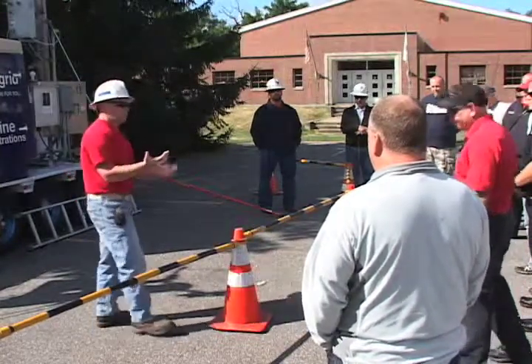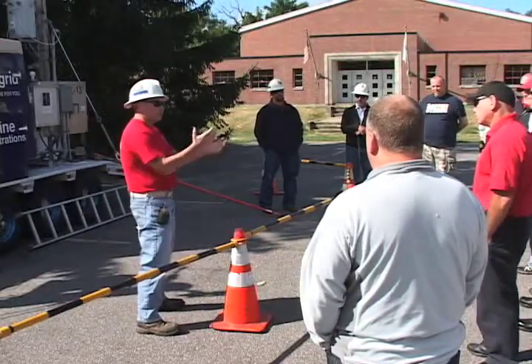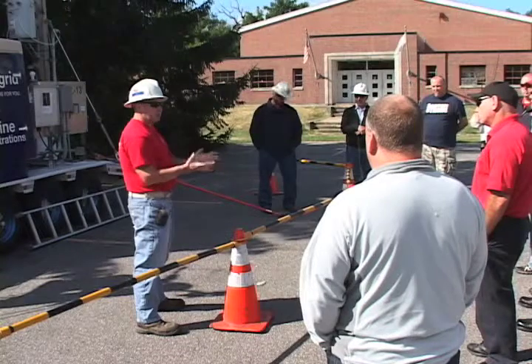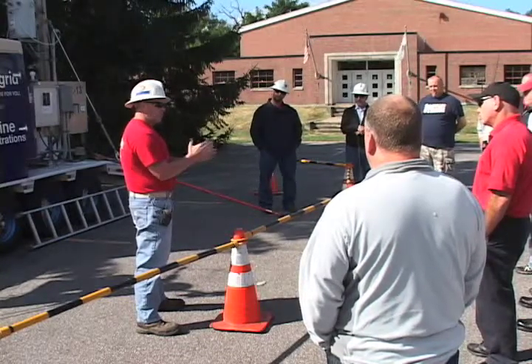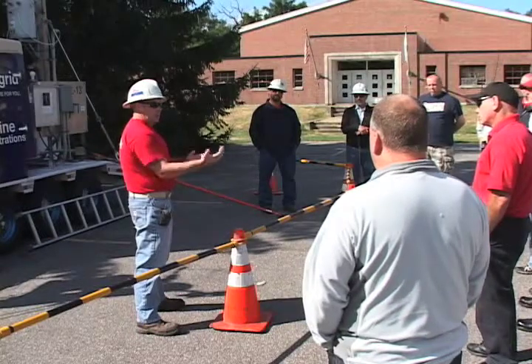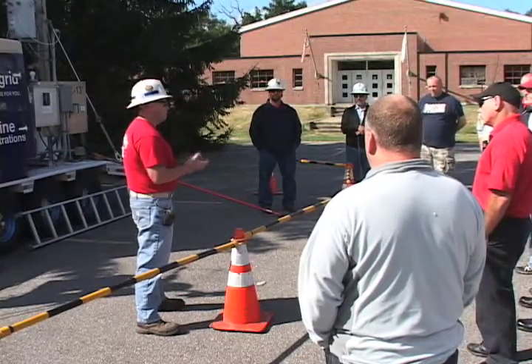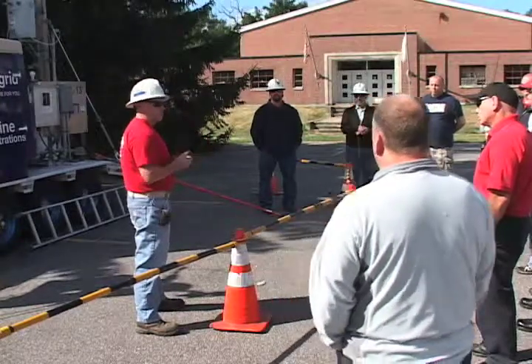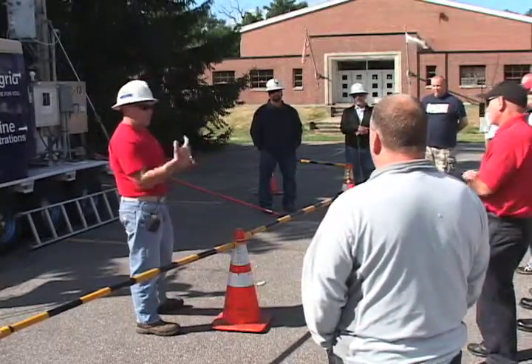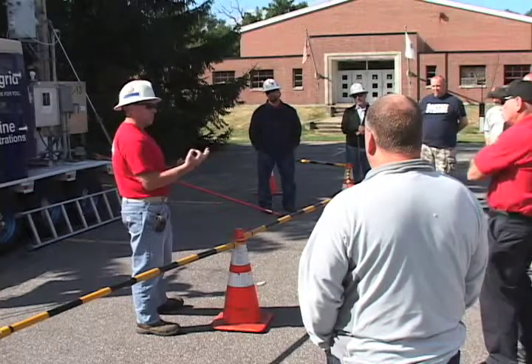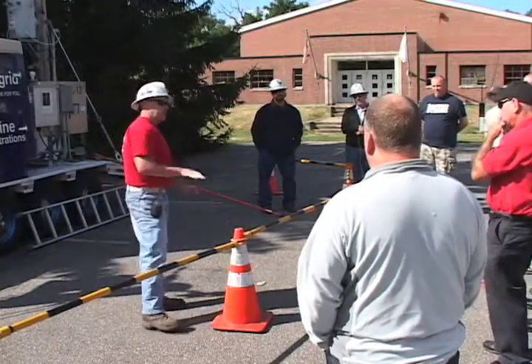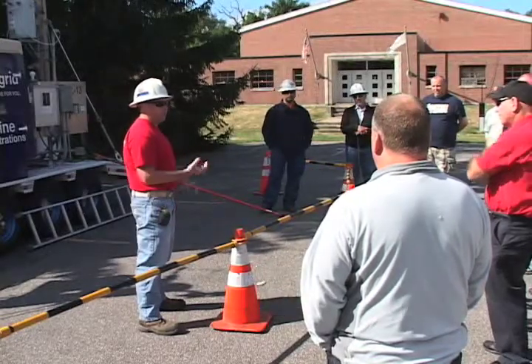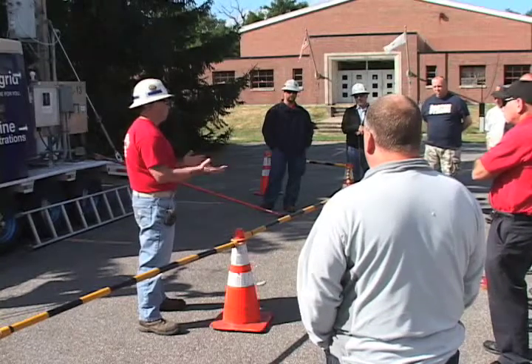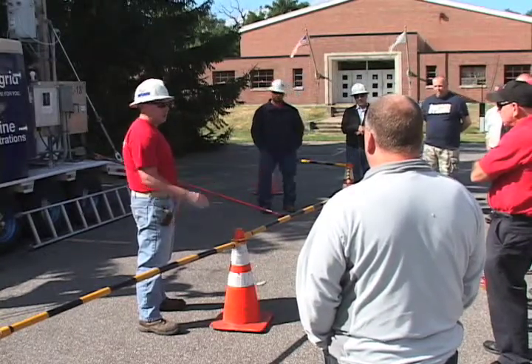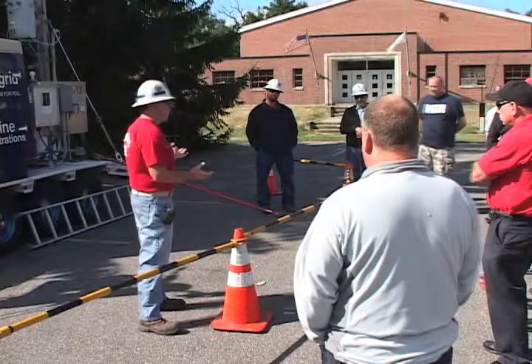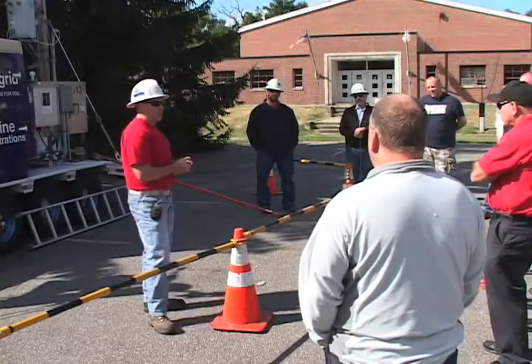When a tree branch, bird, or squirrel causes a fault across the power lines, the recloser sees it and opens up for a couple of seconds. After that time, it closes back in. If the branch or animal has burnt or blown off, everyone's fine and the lights stay on. But if it's still there, it opens again for another 3 seconds, repeating up to 3 times. After the third time, it stays locked out, and that's when we physically come out to patrol and find the problem. That's why your lights might flicker on and off a few times before staying on or off.